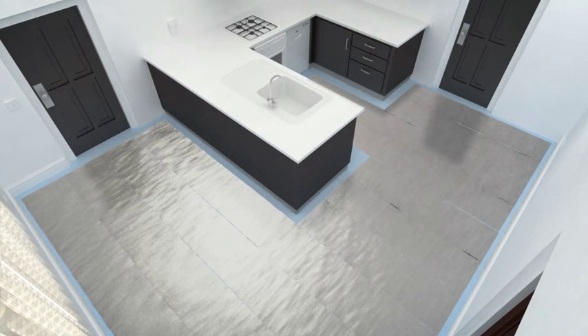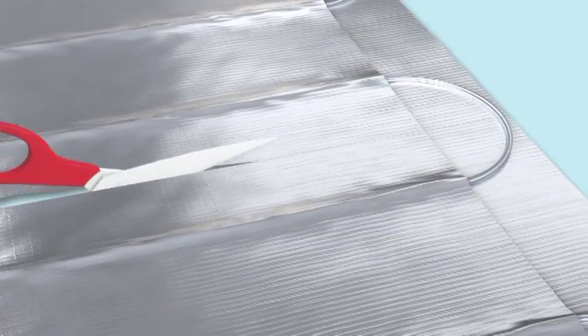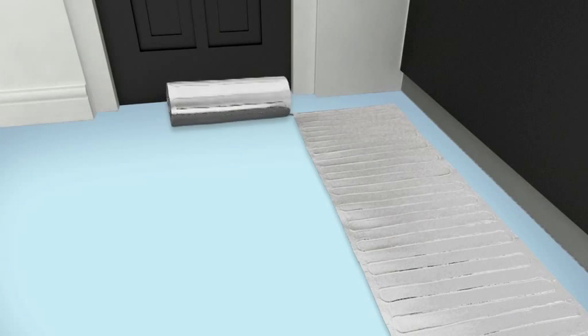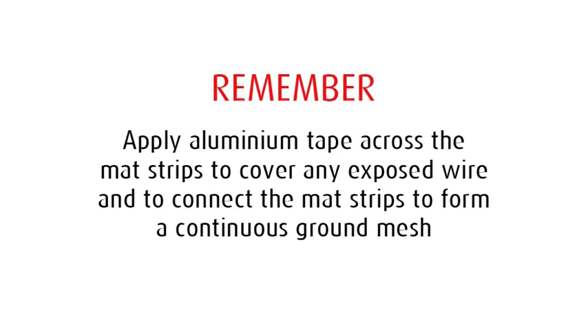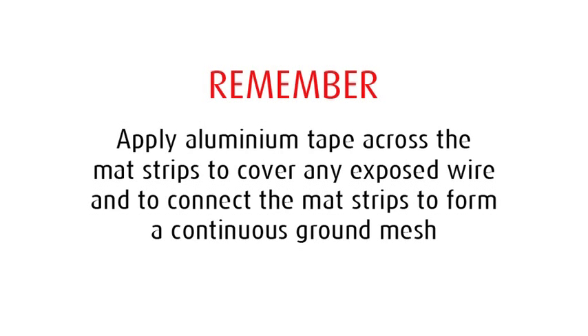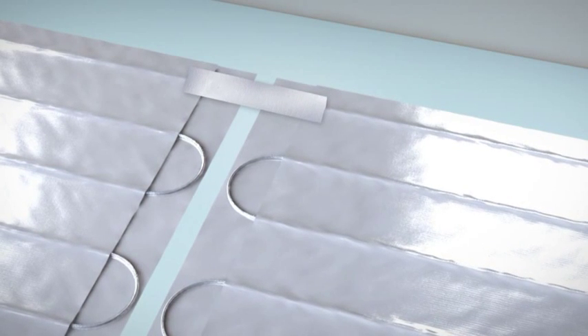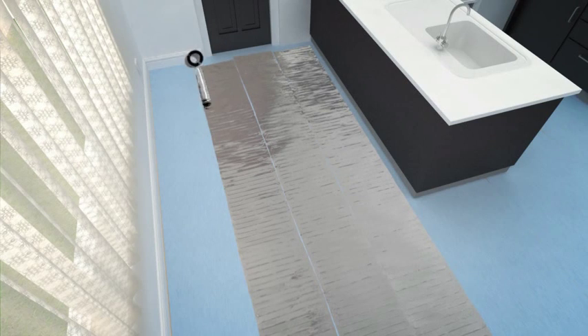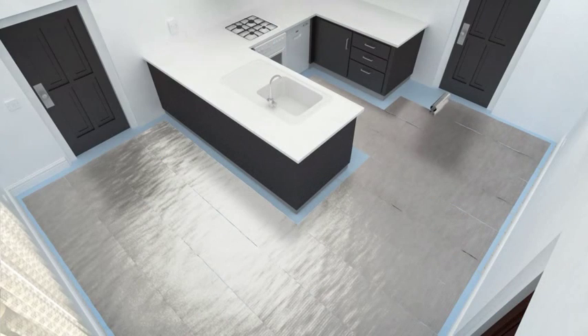The foil heating system can be cut and turned and modified to fit to a specific area. Never cut the heating wire and be careful that the ground braid that surrounds the heating conductors remains intact. When you cut the foil, apply aluminum tape across any exposed heating cables between two adjacent heating panels, ensuring that there is a continuous ground mesh.